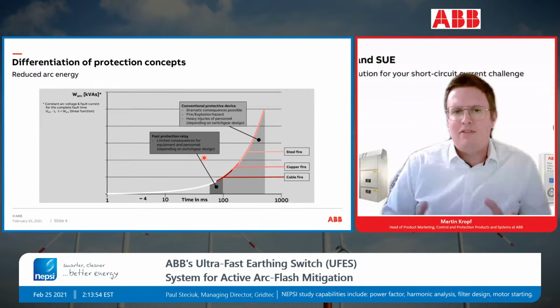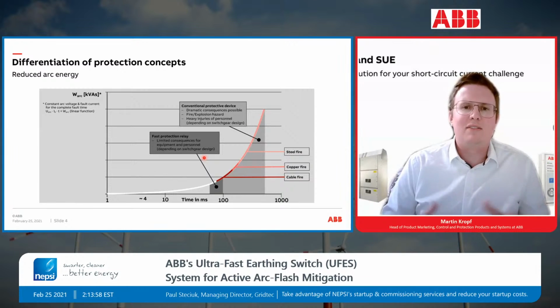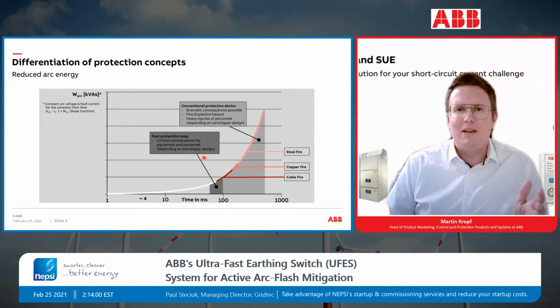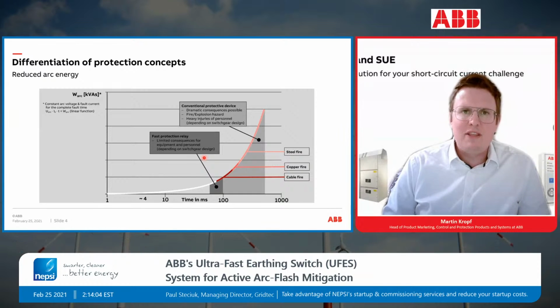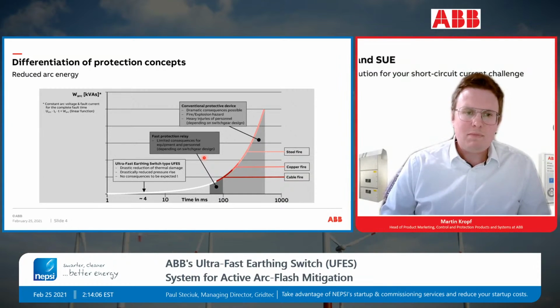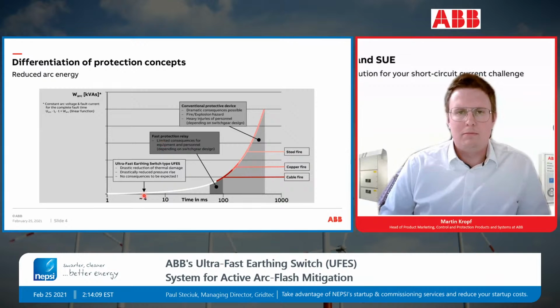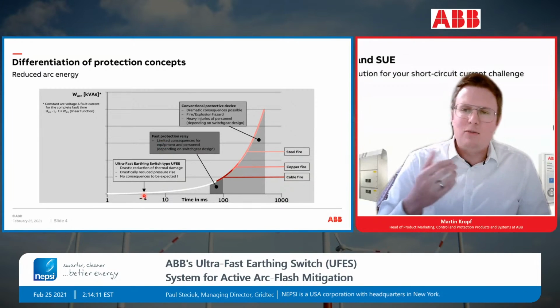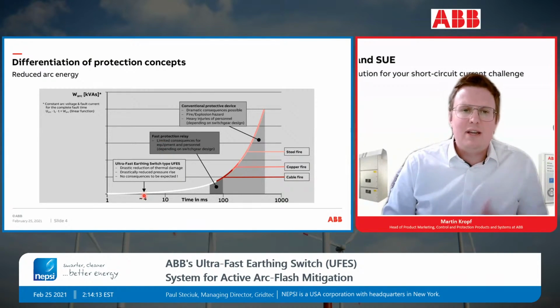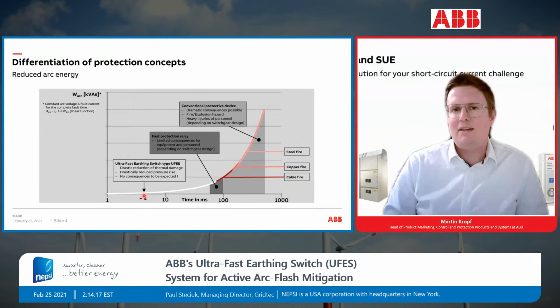So you see here now, fast detection, great, 2.5 milliseconds, for instance, and the breaker takes then another 50 to 80 milliseconds. So we have to find another way, and this we have done with the ultra-fast earthing switch, and we are down at 4 milliseconds. And this means really, as it's written here, actually no consequences to expect. To make it short, you can clean away a fault. And this is the key thing.